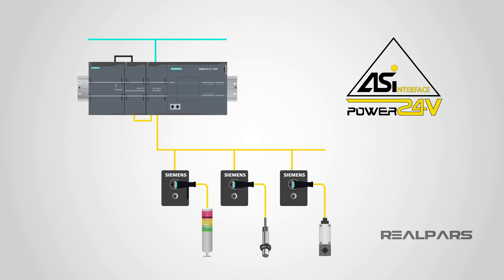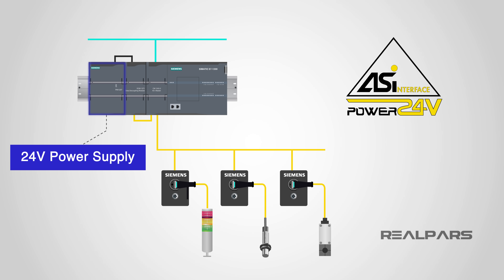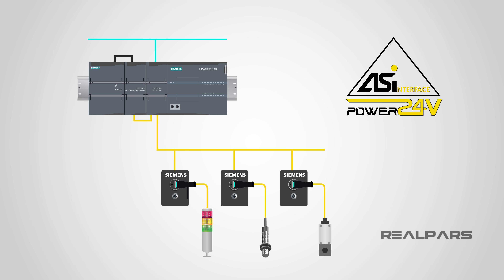Then we have ASI Power 24 volts. We know that the AS Interface can carry both power and data on the same cable, so you might be wondering what ASI Power 24 volts does differently. What it does is utilize standard 24 volt power supplies, meaning that the 30 volts DC power supplies are not needed. This type of device works well in small systems, because the distance the power and data can travel is reduced to around 50 meters, but it can maximize cost savings by not having an additional power supply to purchase and the required space to house it.